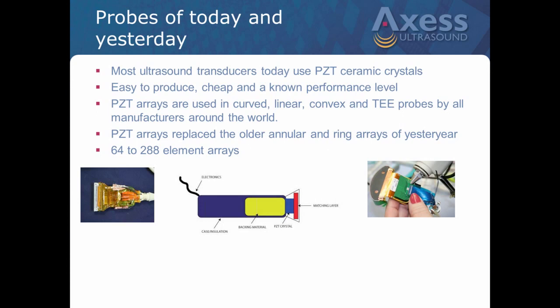Now today, and this is just getting into some materials, kind of give you a baseline of what probes are, how they're built and what they're made of today. Most ultrasound transducers today use a composite material, commonly called PZT. They're ceramic crystal arrays. One of the reasons that most manufacturers use those currently, they are easy to produce, very repeatable from a manufacturing perspective, little waste. They're very good at making them, the array companies, as well as the ultrasound OEMs themselves. Relatively cheap, relative as always, and they have a very well-established performance level. So there's not a lot of issues with acoustic power and so on. The manufacturers know what they're going to get out of these arrays.